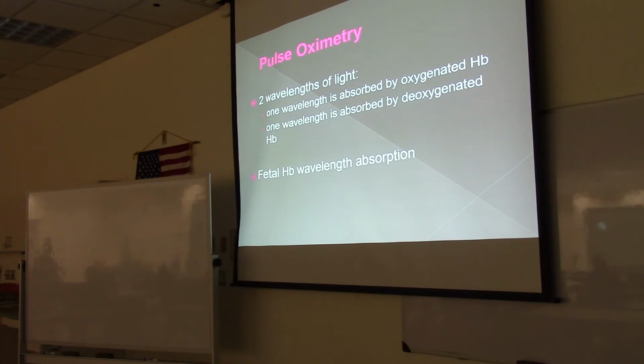With pulse oximetry, we know that it works by sending 2 wavelengths of light through the finger. One wavelength of light is absorbed by hemoglobin that has oxygen. The other wavelength of light is absorbed by hemoglobin with no oxygen. And from that, it sets up a percentage, and that's where you get your oxygen percentage. The second bullet says fetal hemoglobin wavelength absorption. It's the same as adult hemoglobin, so no need for a different monitor.